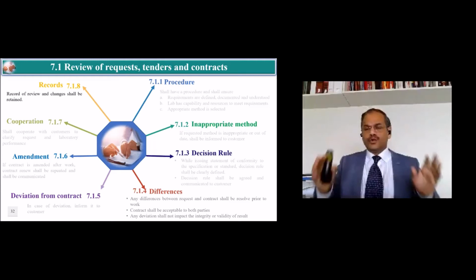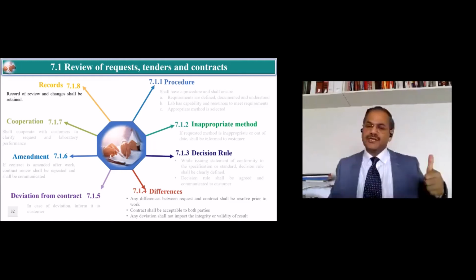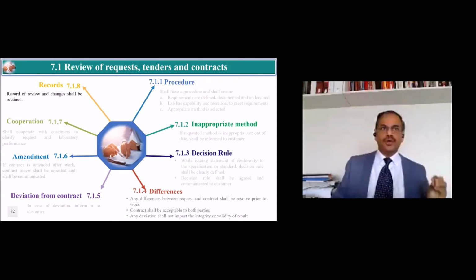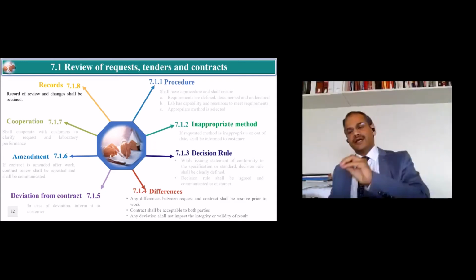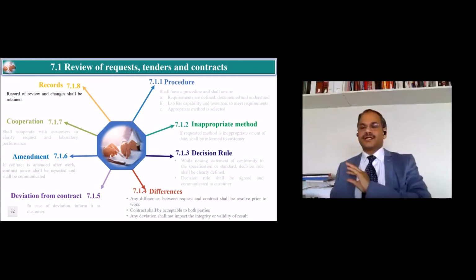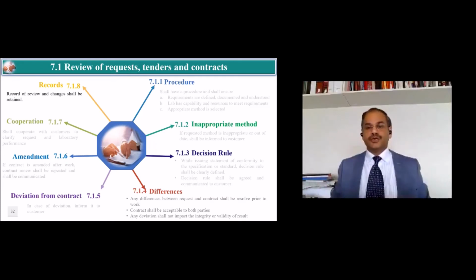procedure for how you are going to handle the requests or the contracts. How are you using the appropriate method which is required to perform the testing or the calibration? Whether it is provided by you, provided by a legal entity, provided in the contract, provided by the customers, or no one has provided, are you going to use an appropriate method? If they give you an inappropriate method, saying use this method, you have to say, sorry, I cannot use this method for this particular testing or calibration. You should be very clear on that.